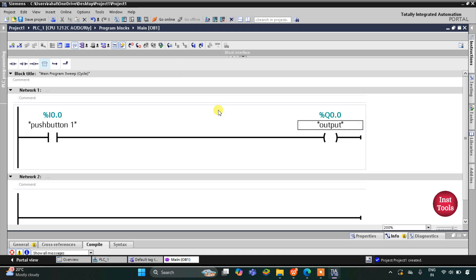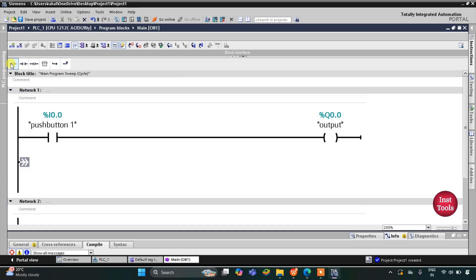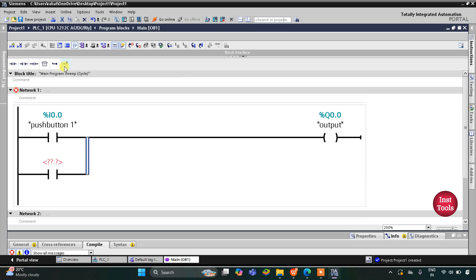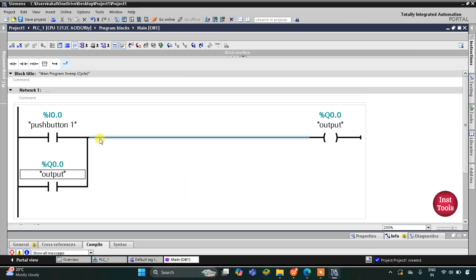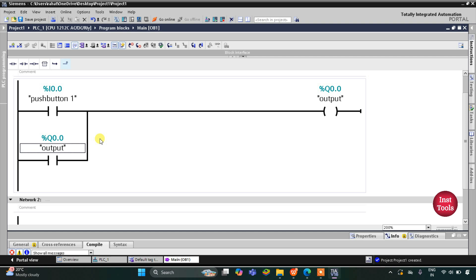When push button is pressed the output will be on, and when push button is released the output will be off. But after releasing push button one, the output should remain on. For that we will latch the output by connecting the output as a normally open contact in parallel with push button one. So now when push button is pressed, output will be on, and when released, output will still remain on.